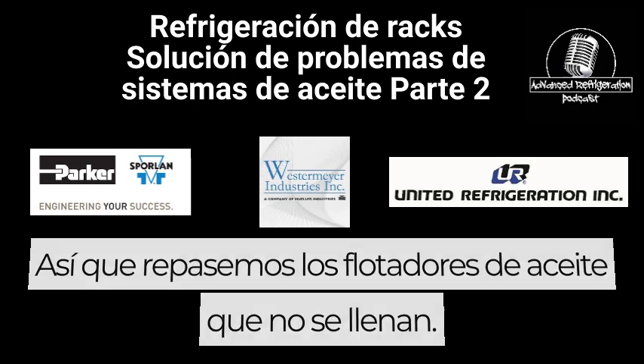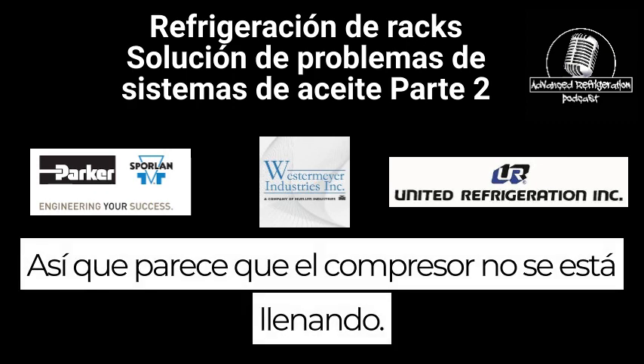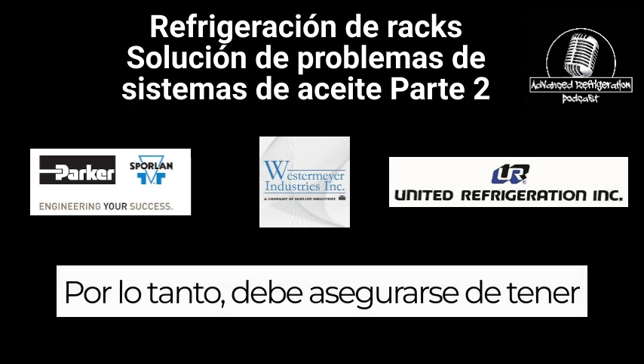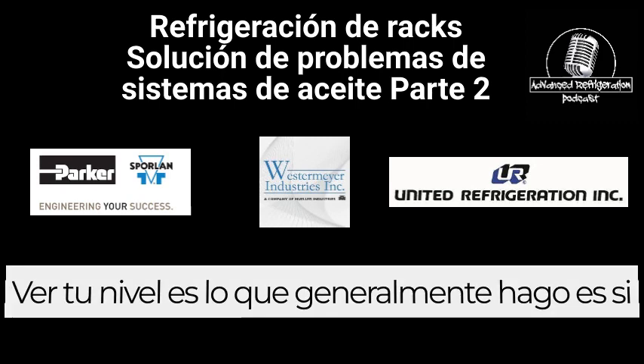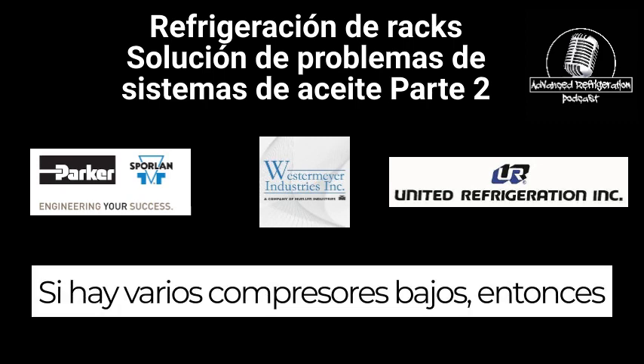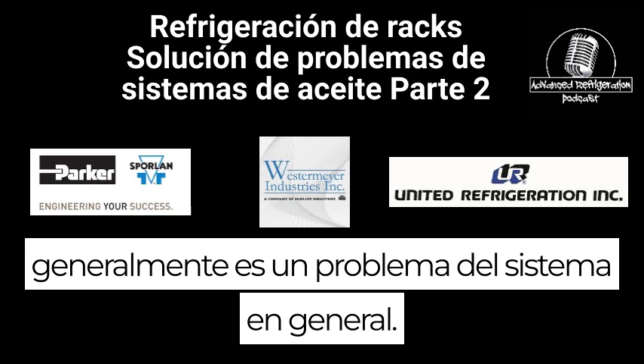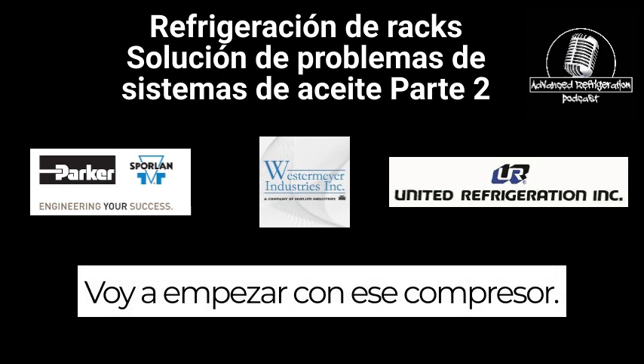Great. So let's go over oil floats not filling, or compressors not filling. It's another big one. First and foremost, look at your compressor and see what your level is. What I generally do is, if it's one compressor, it's usually related to that compressor. If it's multiple compressors low, then it's usually a system issue. Generally. So if it's one compressor, I'll start with that compressor.